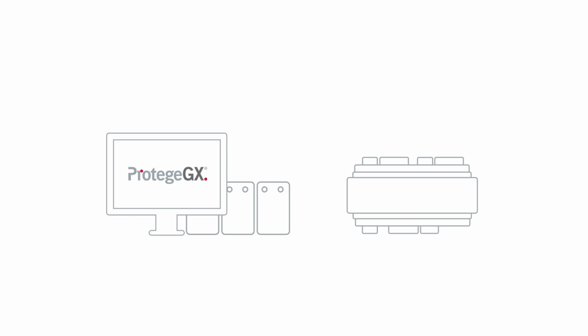Step 2 should be making sure that the static IP address on your server is in the same range as the IP address of your controller. For example, if your controller is on a 192.168.1.2 address, your computer should be on a 192.168.1 range as well.